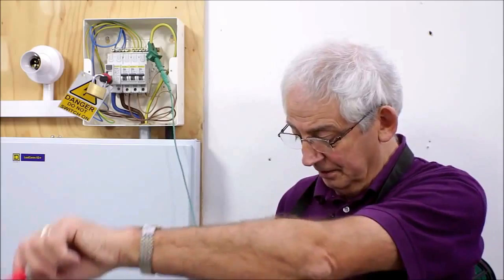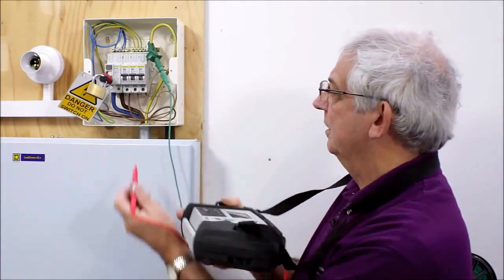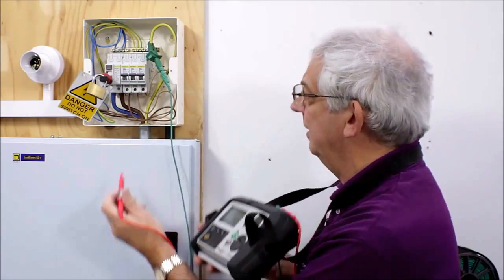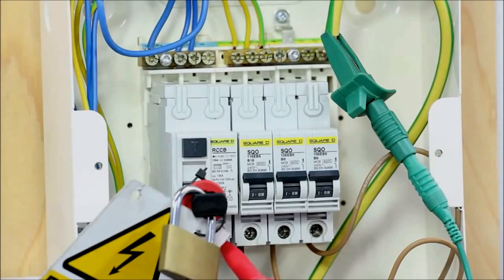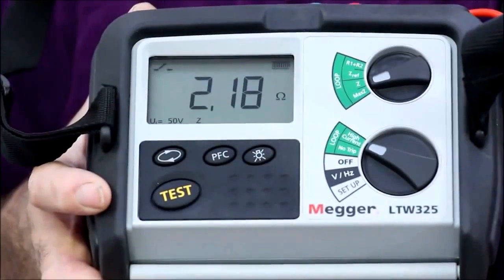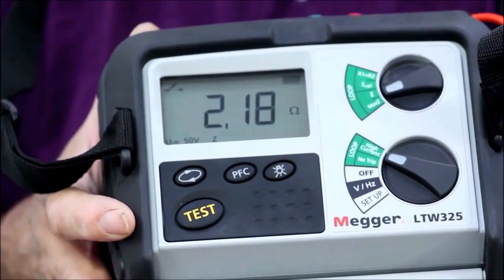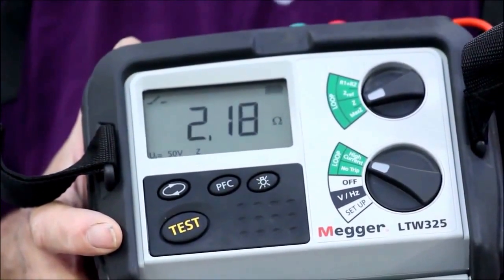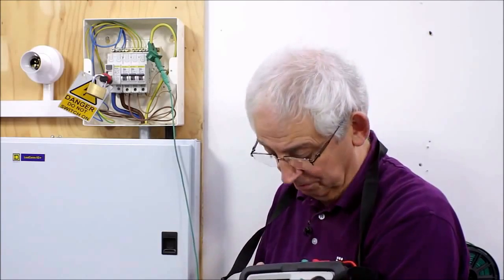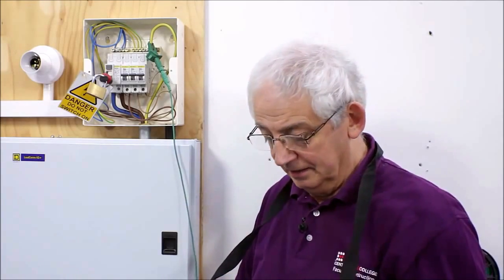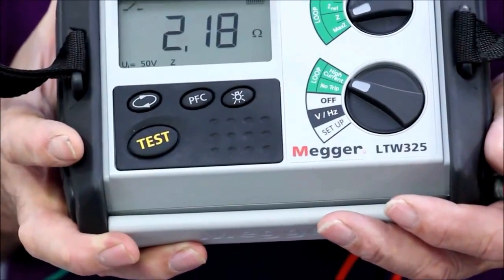turn my earth loop impedance tester to high current because there are no RCDs in this circuit, and then I'm going to take a test between the incoming line, and you can see there we've got a reading which is 2.18 ohms. That's quite low for an earth electrode. The reason for that is that it's very, very wet outside. It's been pouring with rain for ages, and consequently we're getting a very good reading.